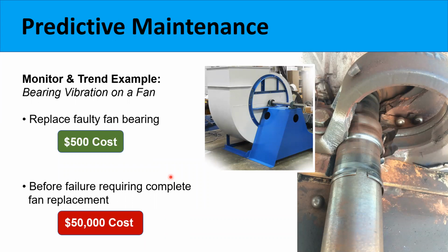Here we have an actual customer example in which they ignored their fan vibration issue just one too many times, only to have the inboard bearing, you can see there on the right-hand side, catastrophically fail and ultimately tear apart, damaging not only that bearing, but it also damaged the shaft, the fan's drive, impeller, and the fan housing. So typically, the cost to replace a set of bearings is usually around $500. In this example, not replacing the bearings in a timely fashion cost approximately $50,000 for just the new fan.